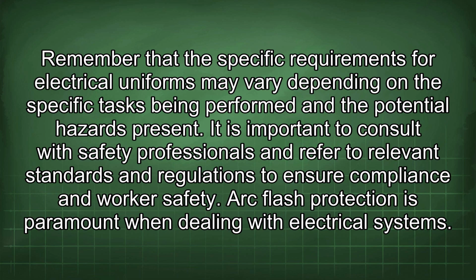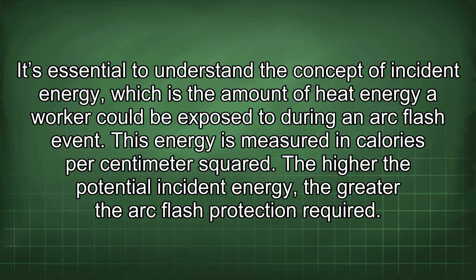Arc flash protection is paramount when dealing with electrical systems. It's essential to understand the concept of incident energy, which is the amount of heat energy a worker could be exposed to during an arc flash event. This energy is measured in calories per centimeter squared. The higher the potential incident energy, the greater the arc flash protection required.